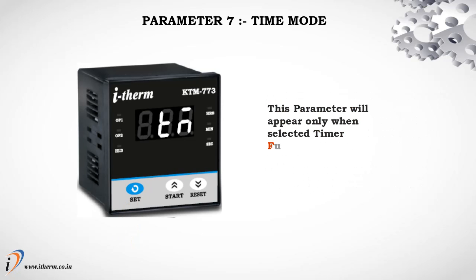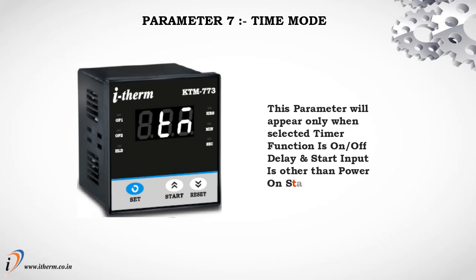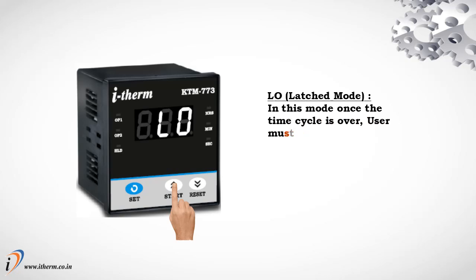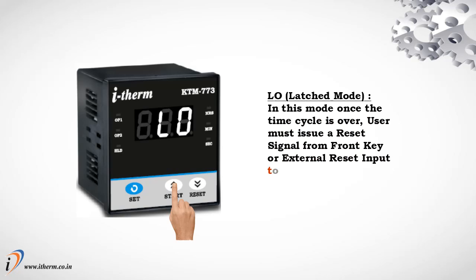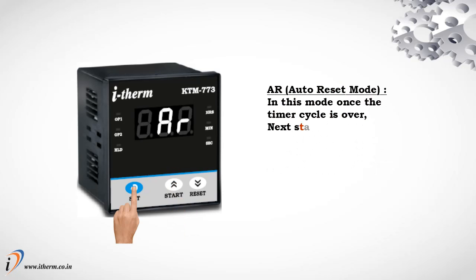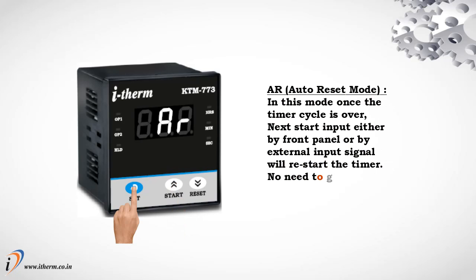Parameter 7: Time Mode. This parameter will appear only when the selected timer function is on delay or off delay and start input is other than power on start. Latched Mode: once the time cycle is over, the user must issue a reset signal from the front key or external reset input to restart the timer. Auto Reset Mode: once the timer cycle is over, the next start input — either by front panel or external input signal — will restart the timer. No need to give a reset signal.